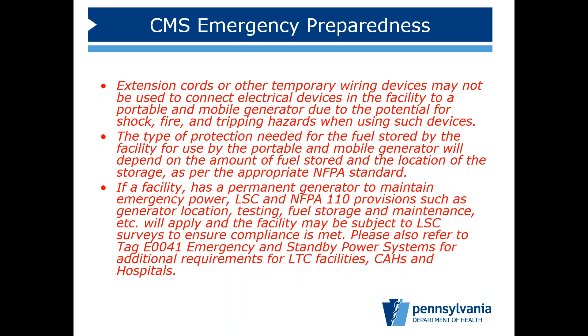The type of protection needed for fuel has to meet the appropriate standards for the facility. If your facility has a permanent generator, which pretty much everybody does, then we have to have all the fuel storage testing -- everything needs to meet the requirements. But when a mobile portable generator is brought in during an emergency, the requirements are a little different because we just need to get you up and running and provide power for the residents.